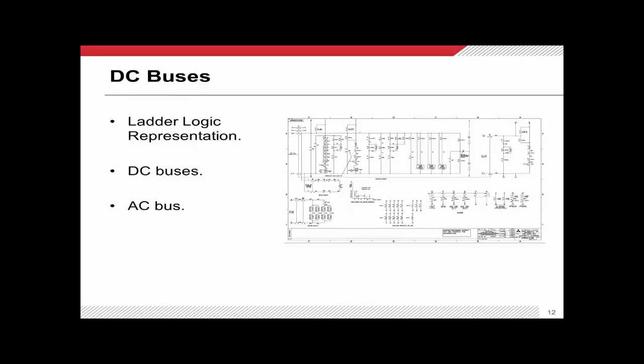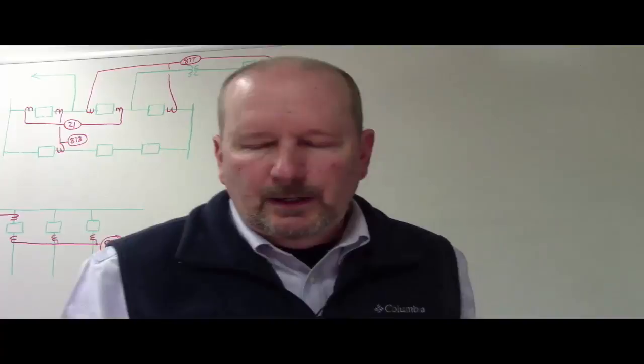We always put heaters in control cabinets to make sure they stay dry. Particularly on cold rainy nights or nights with high moisture, you'll get condensation that can degrade the ability of your circuit breaker to operate over time. If you look closely, half of those heaters are on all the time and half are controlled by a thermostat.